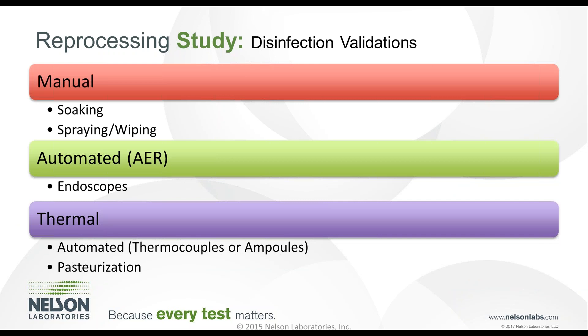The disinfection validation process can be broken out into three main processes, and this is where you'll see some of the differences between the U.S. and European market. Manual disinfection includes soaking, spraying, or wiping — using either immersion or two-in-one wipes, super sani-cloth, heavy wipes, or similar products to spray-wipe the device.